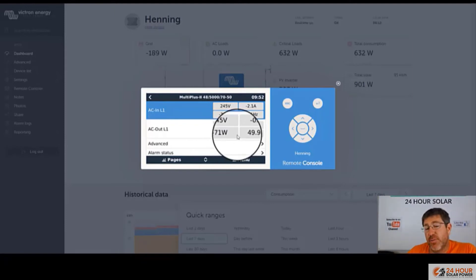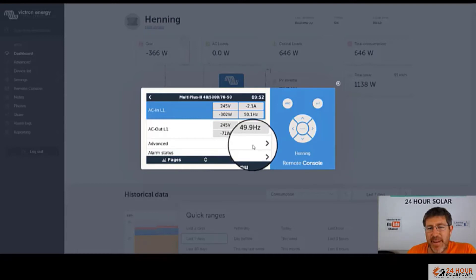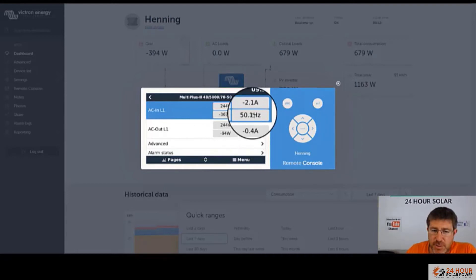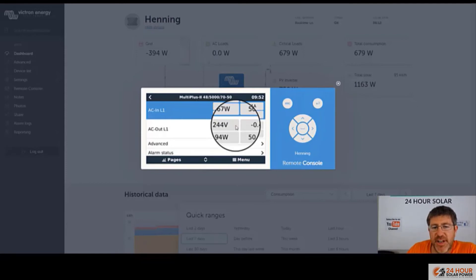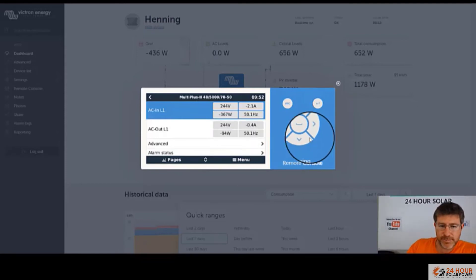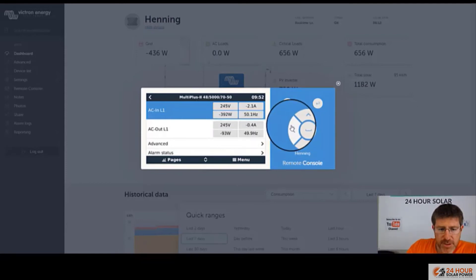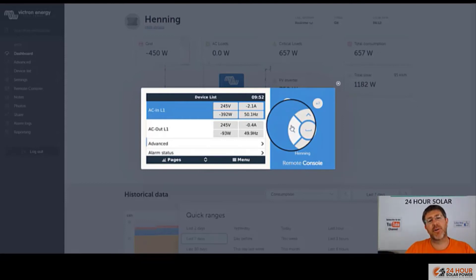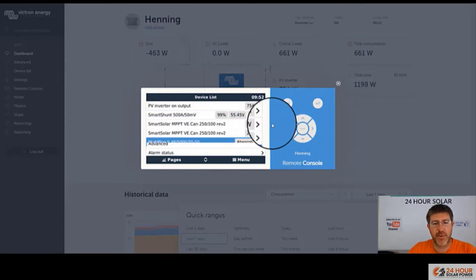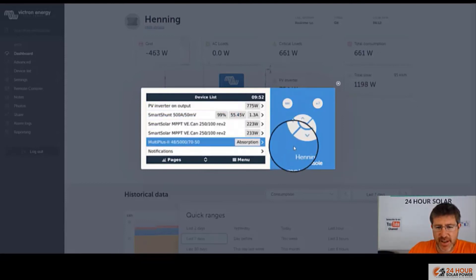It'll ramp up in a minute and it'll feed a load back to the grid, and those grid voltages will rise. So that's a really good thing to have a look. If you're having problems with your PV and it's not just producing and you're not exporting as much as what you think, this is a really good way to go in and check and see what your grid voltages are. If you've got a multi-meter, you can just plug them to the wall. So you can actually see what's going on with the device, what your AC voltages are and all that sort of stuff.